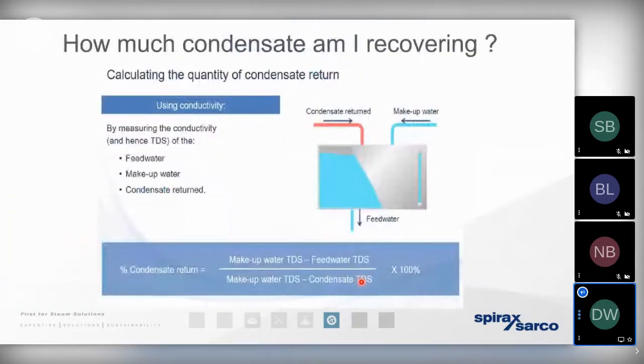So a common question we come across is, okay, our client is aware of the benefits that that hot condensate can bring them. There's no value to the condensate at the process. There's certainly no benefit in keeping the condensate back in the distribution pipework. We need to drain it away. And the one useful area where we can make use of that condensate is by getting it back to the energy center. There's very little energy in the condensate compared to steam, but there's a significant amount of energy compared to cold water straight from the mains.